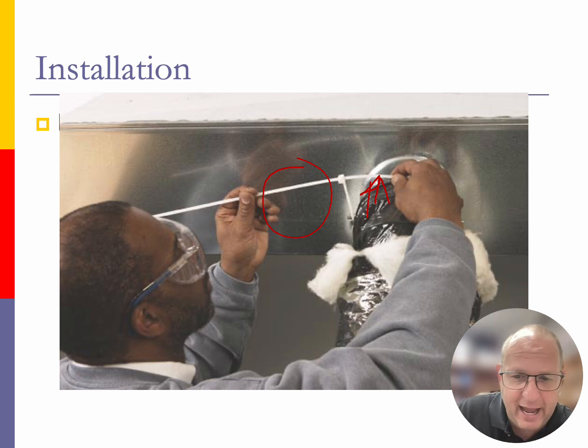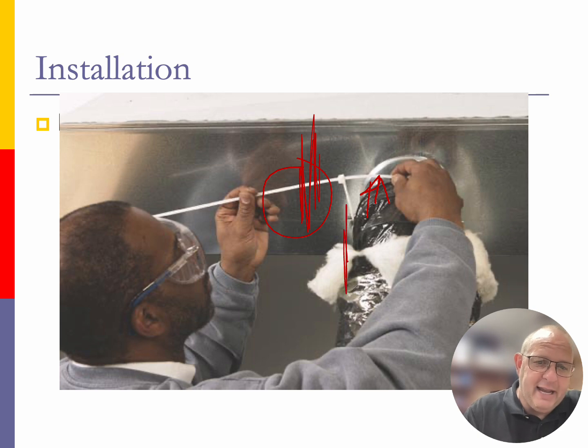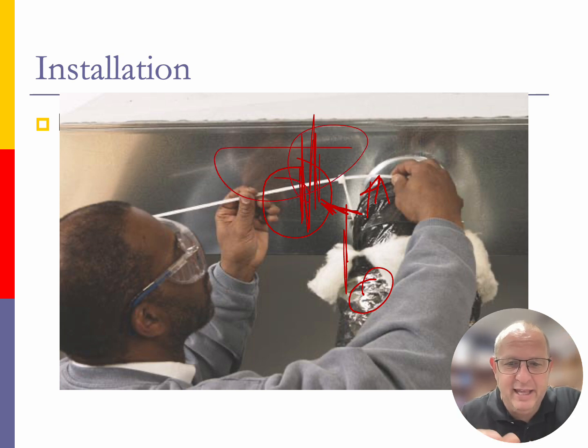that particular flex duct. Now after that, I use duct tape at this point, and I'm going to duct tape that vinyl against the metal with my mastic around the gaps of the metal to metal application that's there. Now after that, I'm going to roll that insulation over top of that takeoff, and then hopefully we're going to have some insulation sitting on this metal pipe, and I'm going to tape this foil back insulation that's on my flex duct to the foil back insulation that's on my rectangular pipe right here. Give me a nice, tight, vapor seal insulated pipe running to my different distribution boots into my areas for that system itself.